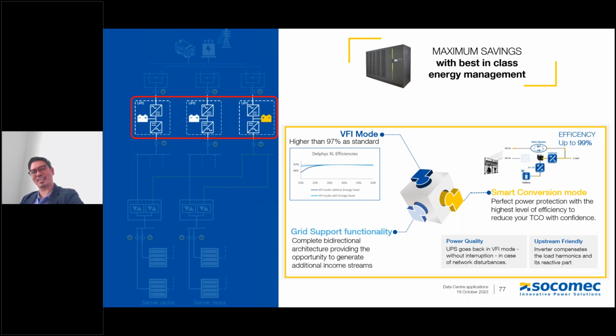Some countries are already implementing this, especially in Europe, and in Australia we have grid authorities that allow data centers to load shed. They can be triggered to remove some load during peak demand so secondary reserves can be activated. Other applications like peak shaving can also be performed using grid-interactive modes.